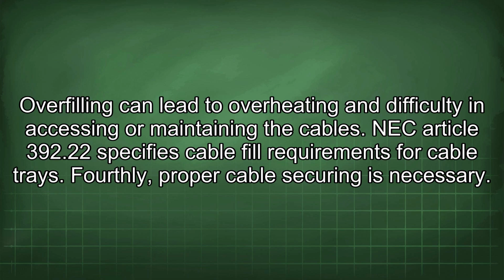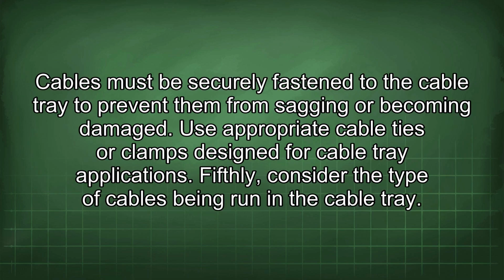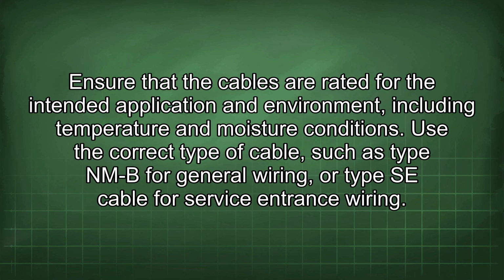Fourthly, proper cable securing is necessary. Cables must be securely fastened to the cable tray to prevent them from sagging or becoming damaged. Use appropriate cable ties or clamps designed for cable tray applications. Fifthly, consider the type of cables being run in the cable tray. Ensure that the cables are rated for the intended application and environment, including temperature and moisture conditions. Use the correct type of cable, such as type NM-B for general wiring, or type SE cable for service entrance wiring.